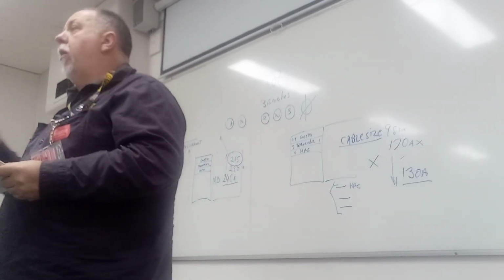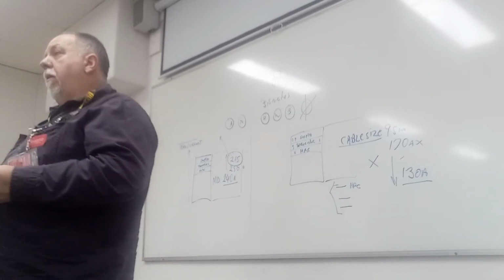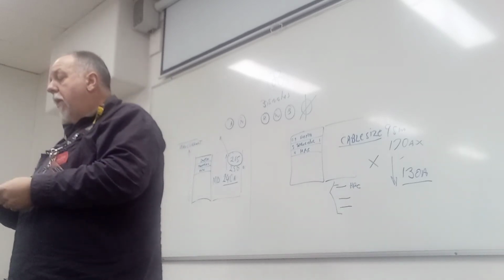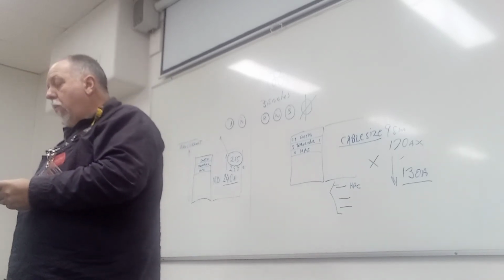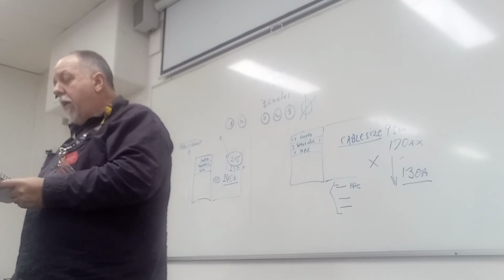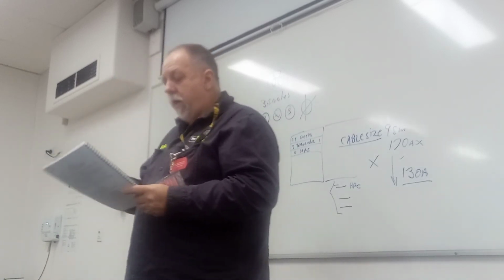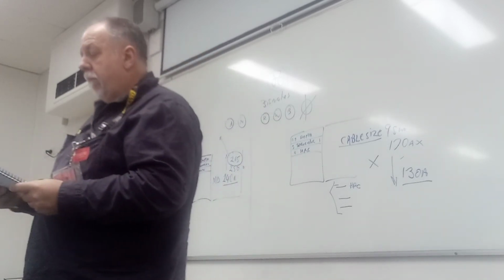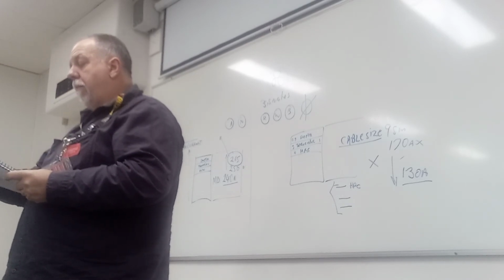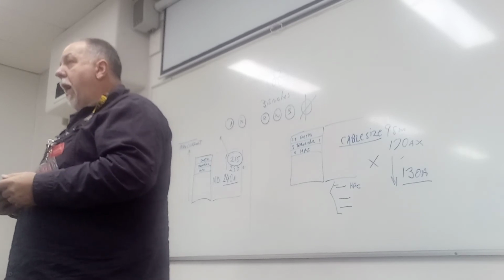So that means if you've got a 1, you don't have to do anything. It's the reason I tell you to highlight it, that if it's either side of that 1, you then have to apply that derating. Depth of laying, we all looked at that, 28.1 and 28.2. Those are there, 0.5 is your derating, same with the top there, 0.5. The only difference between these two is one's buried direct in the ground, the other one's got a wiring enclosure. The problem you've got with the buried direct in the ground, it says up to 50, it talks about 50 millimetre size of cable, not 50 amps.